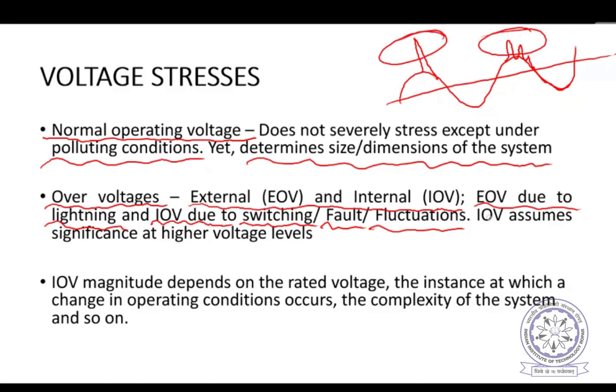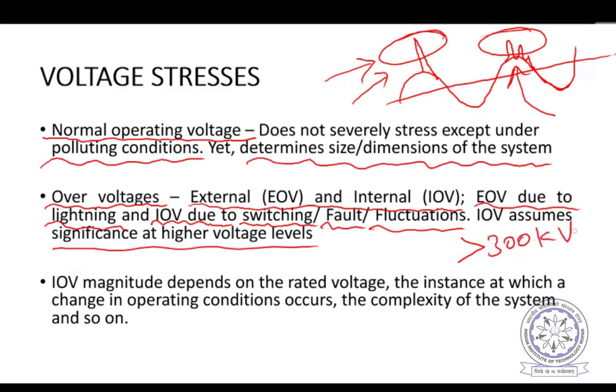With higher voltage levels, what will happen? The lightning voltage maximum magnitude is fixed. The first one is lightning, the second one is switching. The switching over voltages assume importance as the voltage level increases. For example, above roughly 300 kilovolts, switching will dominate over lightning. So we have to concentrate on switching more than lightning if the voltage levels are more than 300 kilovolts.